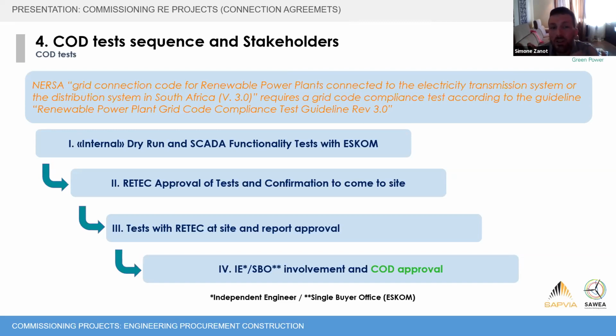But basically we can see 4 stages: we perform the dry run test and SCADA functionality test with ESKOM for our farm. We prepare a report and request approval from RETEC, who comes to site and repeats what was done earlier during the dry run test, checking that the wind farm or solar farm matches the grid code compliance. Then there is a final step where the independent engineer is appointed, acting as the interface with the single buyer office in order to get COD approval.